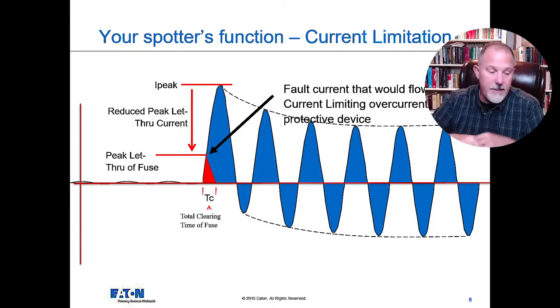This next one is a plastic enclosure — 5,000 amps short circuit current rating with 35,000 amps passing through it. We call them 'biggins' in West Virginia. The equipment could not handle the full brunt force of this waveform. When you protect it by either a circuit breaker or a fuse, you reduce that first half cycle down to something much more manageable — reducing the peak, reducing the duration — which reduces both the magnetic forces and the heat dissipated in the equipment. The equipment never sees the 100,000 or 200,000 amps because the overcurrent device took care of it. Looking at equipment ratings and terms like short circuit withstand capability at half a second or one second — you won't see that duration because the overcurrent protective device limits what the equipment sees.